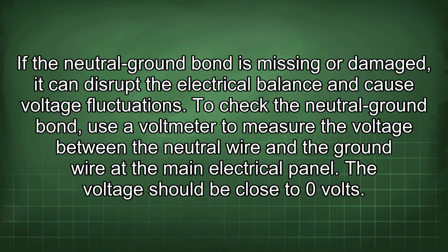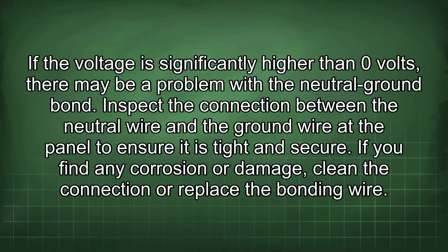To check the neutral ground bond, use a voltmeter to measure the voltage between the neutral wire and the ground wire at the main electrical panel. The voltage should be close to 0 volts. If the voltage is significantly higher than 0 volts, there may be a problem with the neutral ground bond. Inspect the connection between the neutral wire and the ground wire at the panel to ensure it is tight and secure. If you find any corrosion or damage, clean the connection or replace the bonding wire.